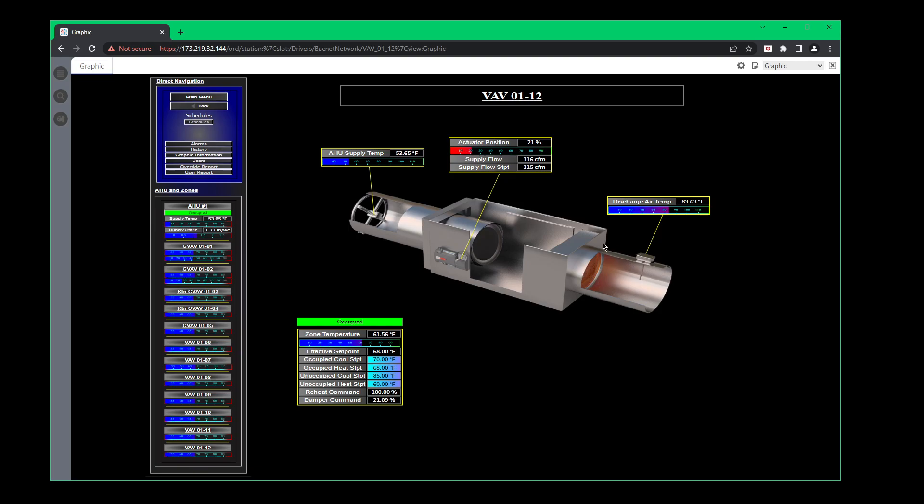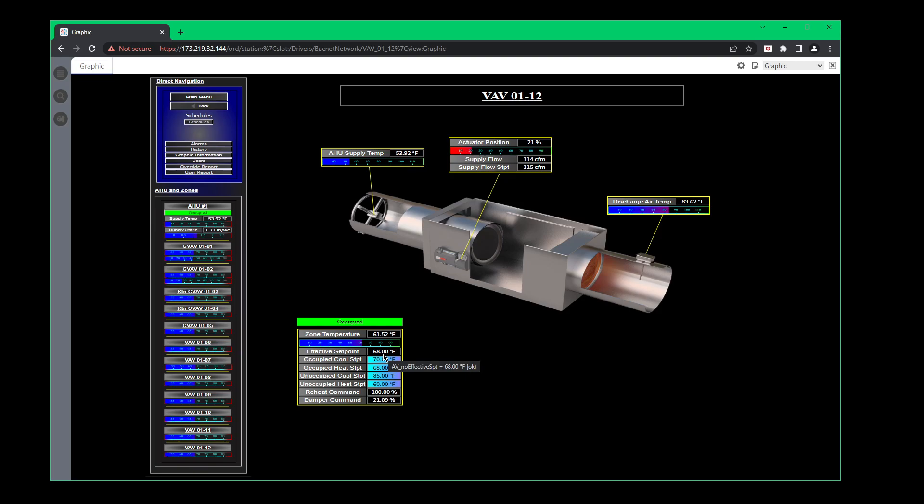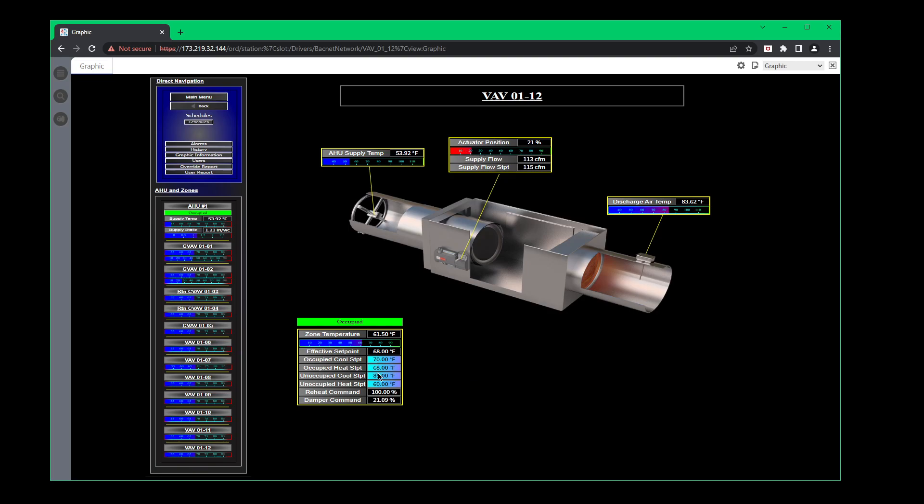If you see this orange right here, that's telling you that your heat is on, obviously. And right here is your discharge air temp. So we have sensors on every discharge on every box down here. You can see that we have the zone temp. Then we have the effective set point. So basically it's telling you what it's trying to control between. So the fact that the occupied heat set point is 68 and your occupied cool set point is 70. These boxes that are in blue are the boxes that you can change, meaning that these are set points.